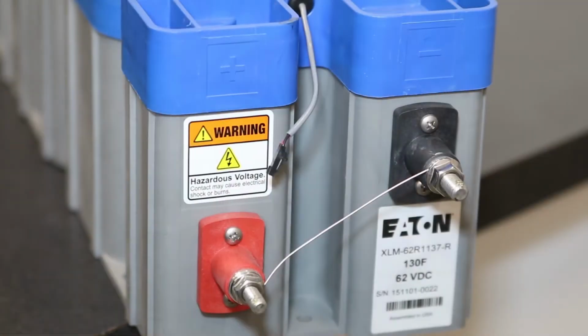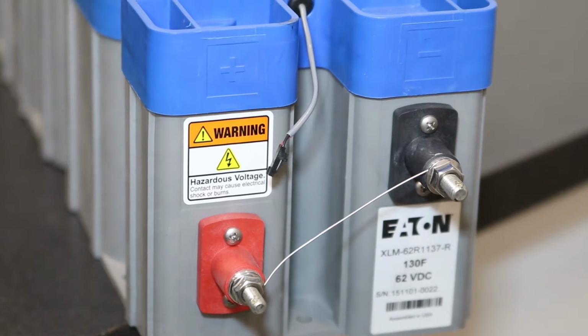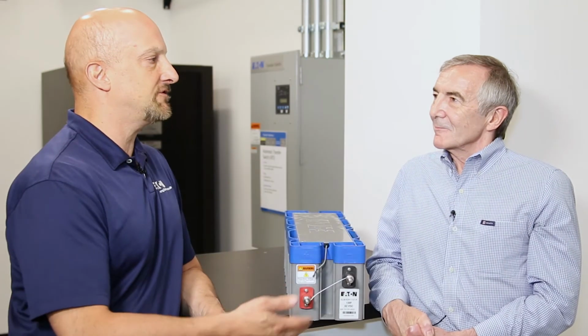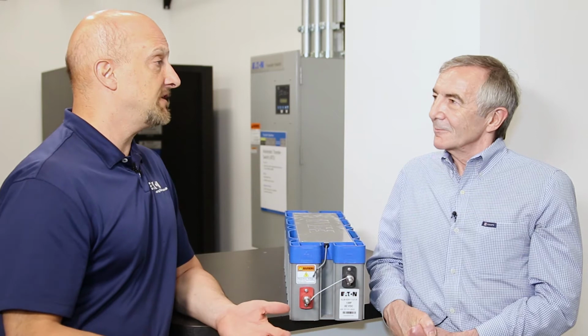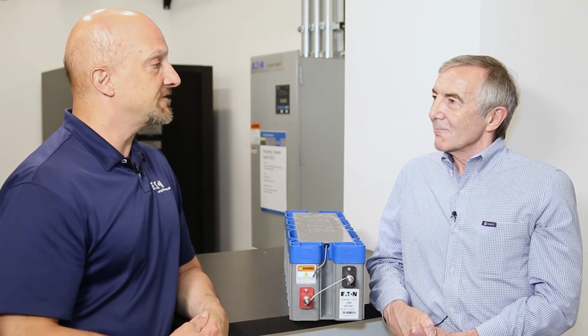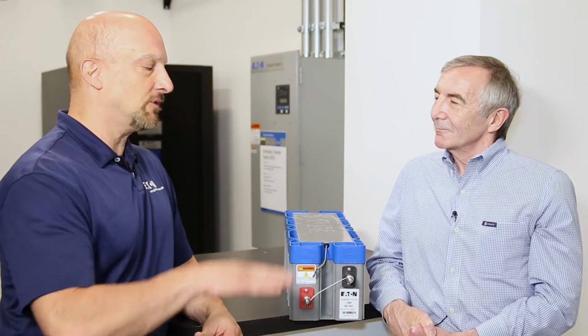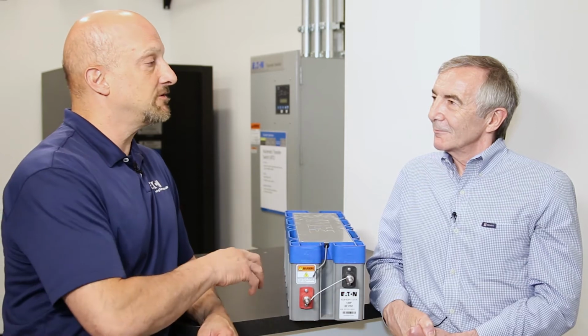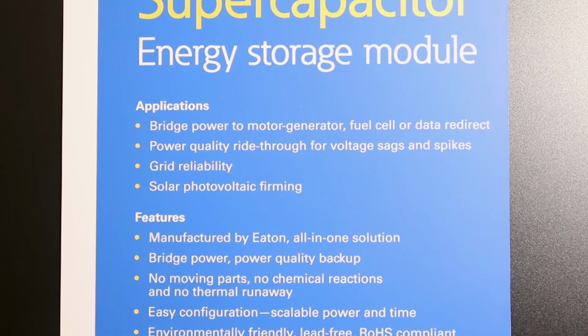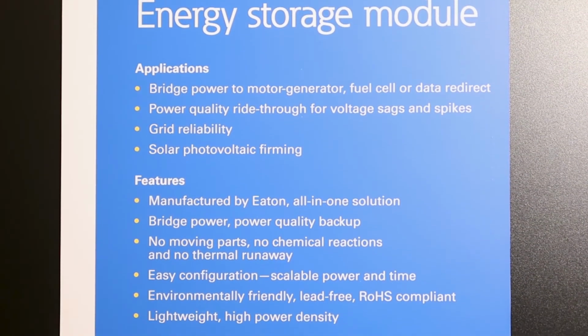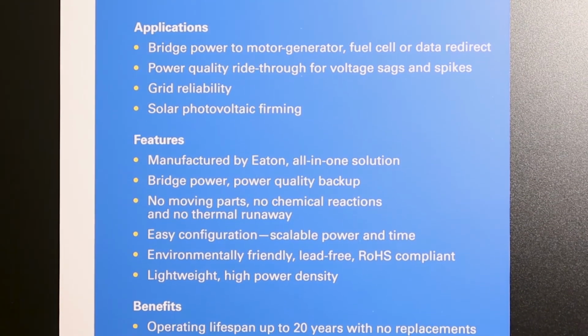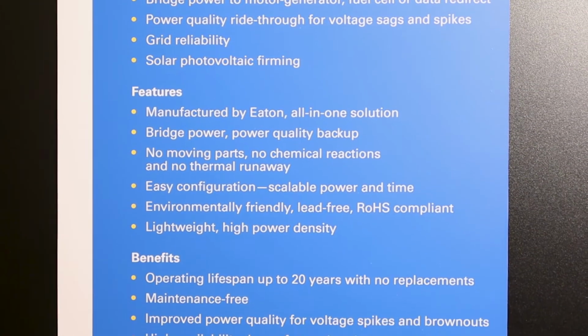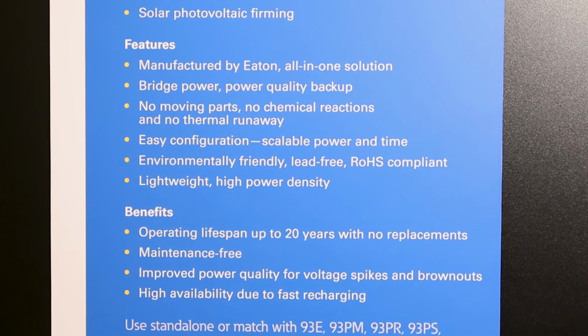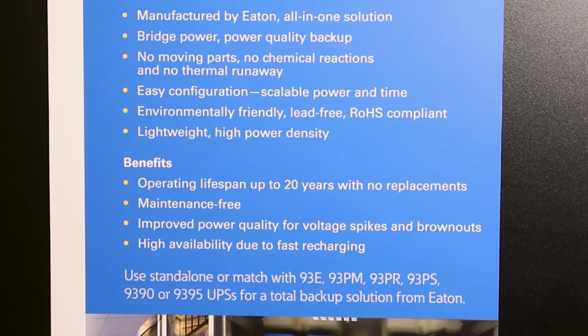But they're very dense, and you get about 15 seconds of ride-through, typically, for a given size. Really all you need is just enough to get to your generator. So if a data center or another system, maybe a microgrid system, just needs a quick discharge of power, 15 or 10 or 20 seconds is usually enough. That 15 minutes you get with a battery backup system is well beyond the time it takes to start the generator.